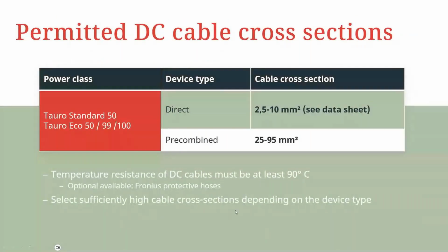Now, in terms of permitted DC cable cross-section area, for the Tauro standard direct version, we implement direct connection from the modules to the inverter using MC4 plugs, so you have 2.5 mm to 10 mm cable cross-section area. For the pre-combined, we have 25 to 95 mm squared on the DC side. Temperature resistance cable must be at least 90 degrees, so please ensure this option is checked.